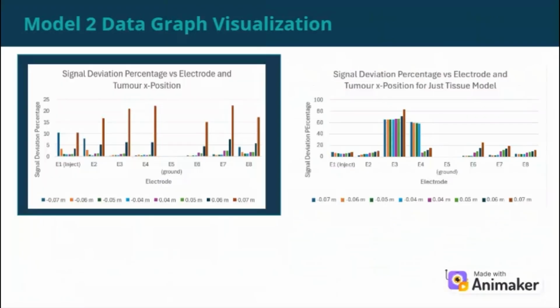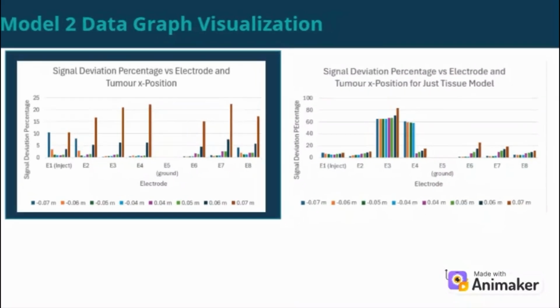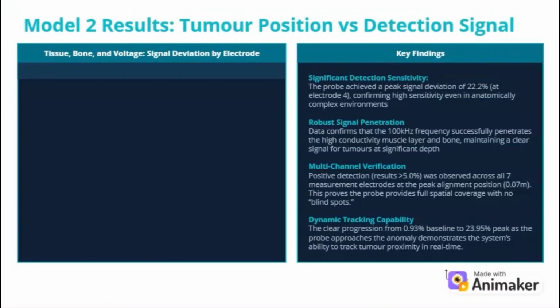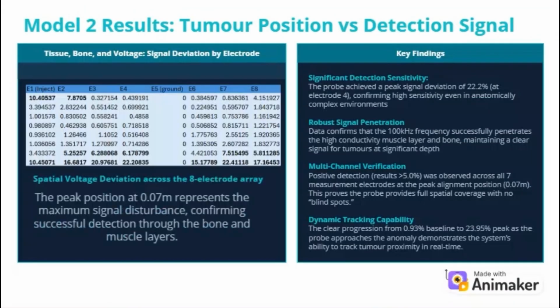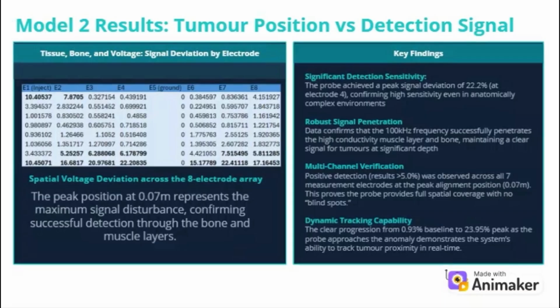This shows the belt design trades localization for robustness in complex anatomy. E3 and E4 are high in the tissue-only case because they sit near the maximum voltage gradient created by the drive electrodes. In homogeneous tissue, the field is smooth and symmetric, so electrodes placed along the dominant current path naturally see larger baseline voltages. Peak signal deviations exceed 20% at optimal alignment. All electrodes register detectable changes, confirming there are no blind spots and that the system can track tumor position dynamically.